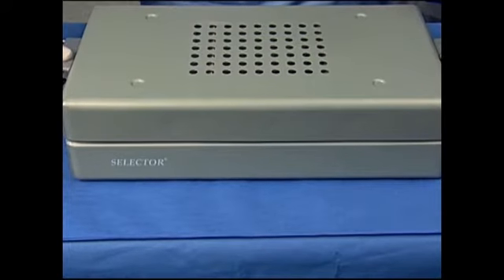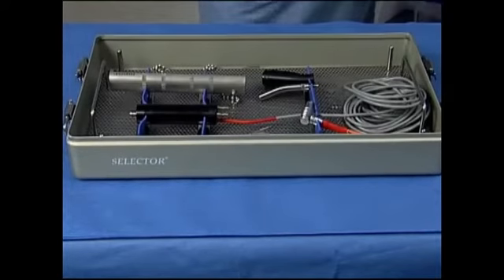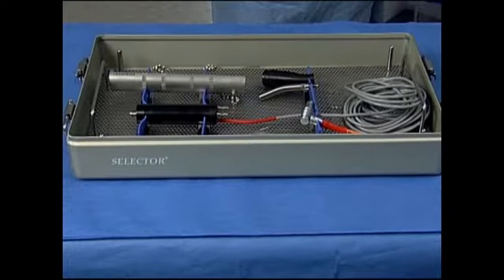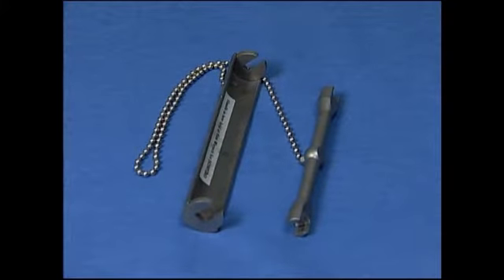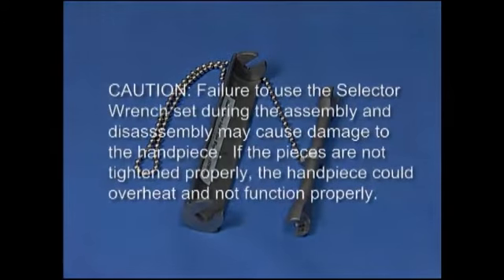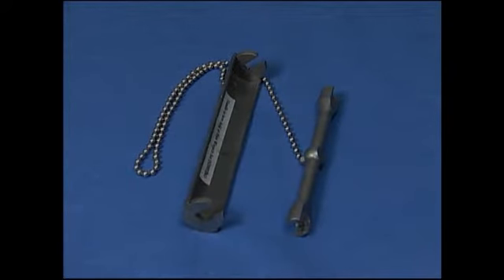Selector handpieces are steam sterilized in the selector sterilization tray. Remove the sterile handpiece components from the tray on the sterile field and assemble the handpiece using the selector wrench set. Caution: failure to use the selector wrench set during the assembly and disassembly may cause damage to the handpiece. If the pieces are not tightened properly, the handpiece could overheat and not function properly. Correct tightening of the joints can be assured only by use of the wrench set.